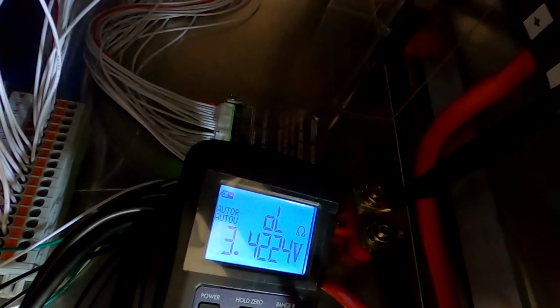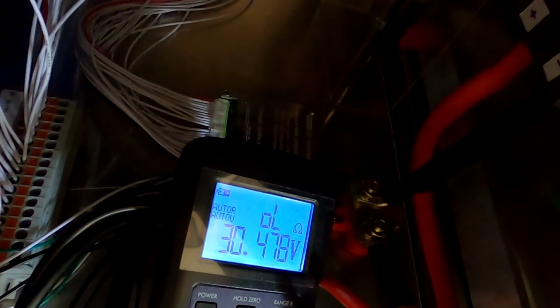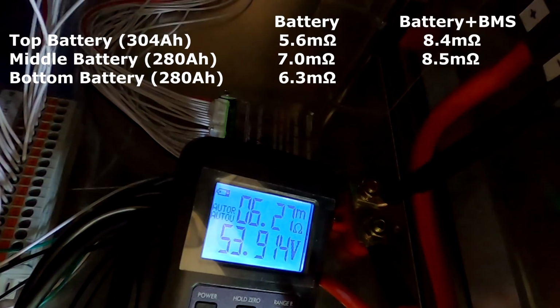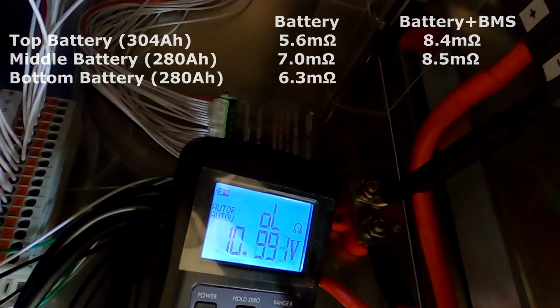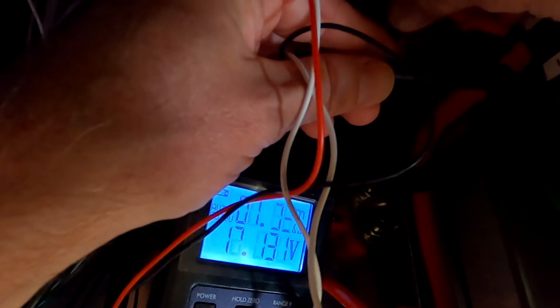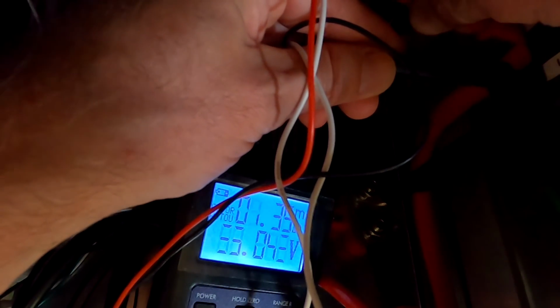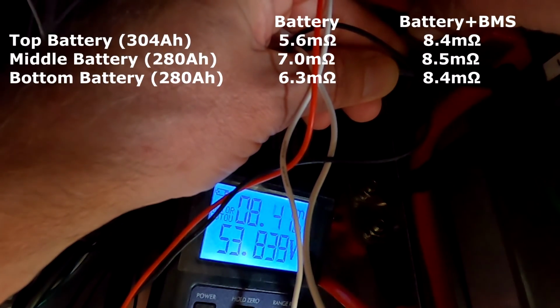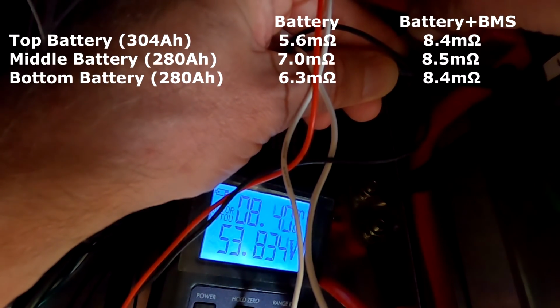Let me do this once again with the bottom battery. Okay, battery is isolated, measuring directly at the terminals, and we've got 6.28 milliohms. Second measurement at the circuit breaker: 8.4 milliohms.